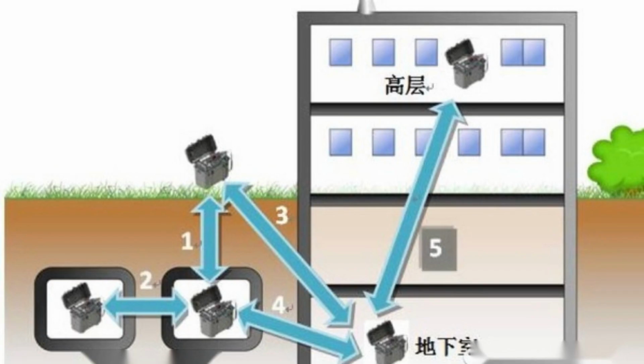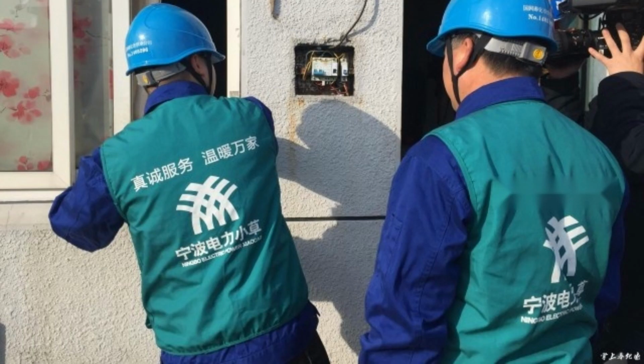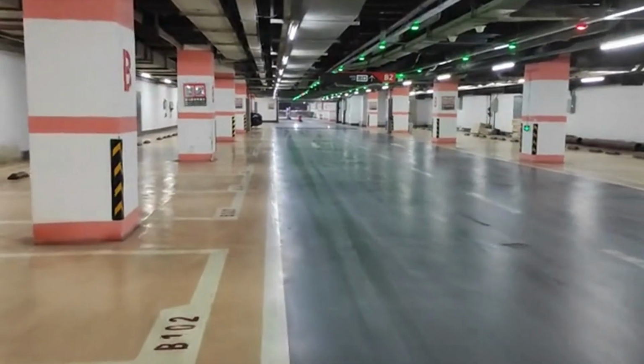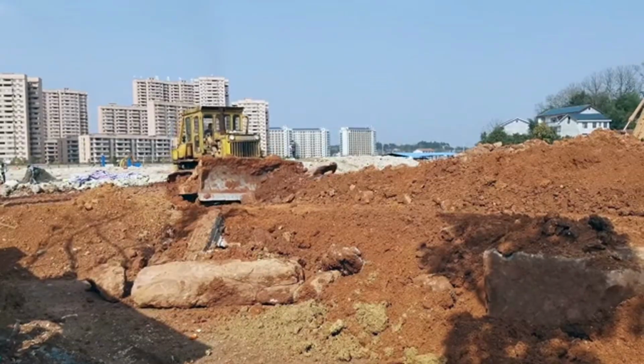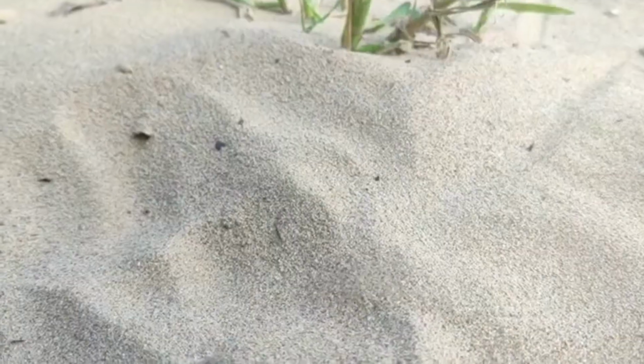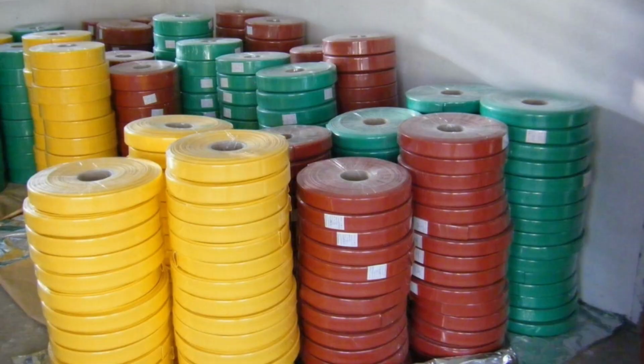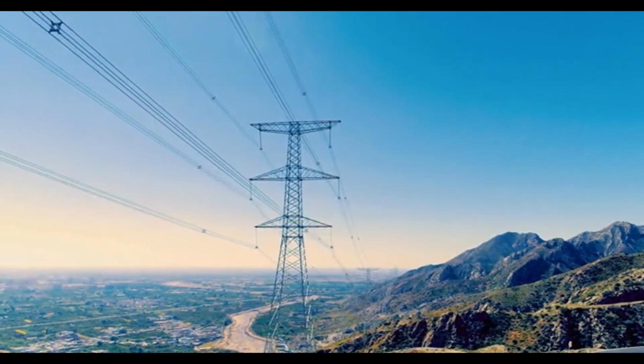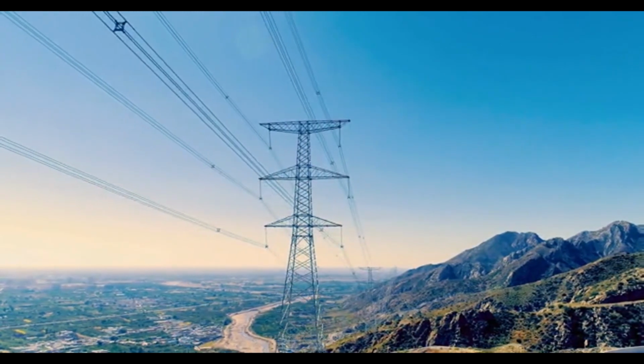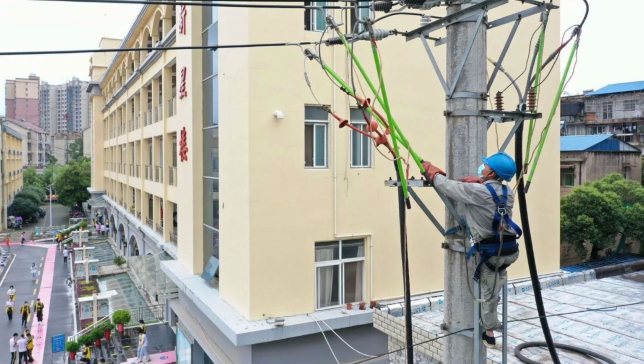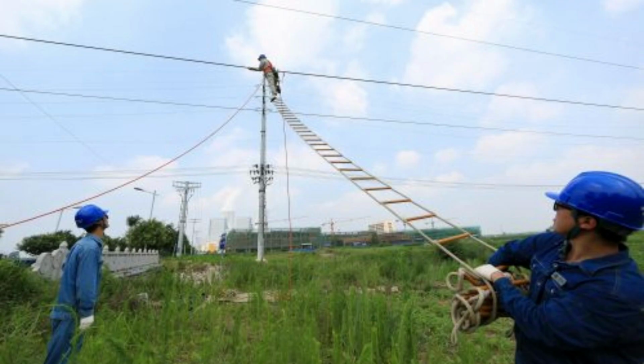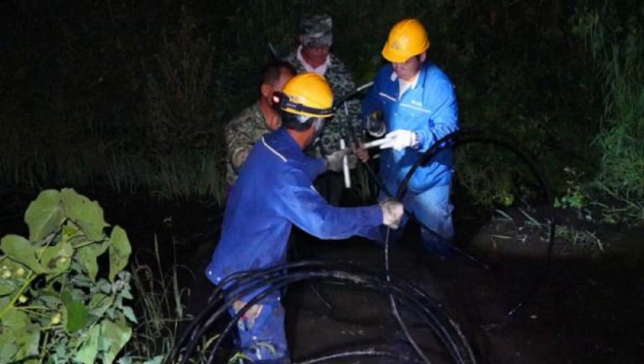What are the main differences between underground and overhead electrical services? As you can see from the name, underground service is run underground, usually 18 to 40 inches deep in a trench, with 6 inches of sand under and over the electrical cable and with caution tape buried a foot above the electrical cable. Overhead electrical service is run from an overhead pole to the house point of attachment, and usually it is triplex overhead rated wire, 6 AWG or higher size. Underground electrical service wiring is safer than overhead electrical service.